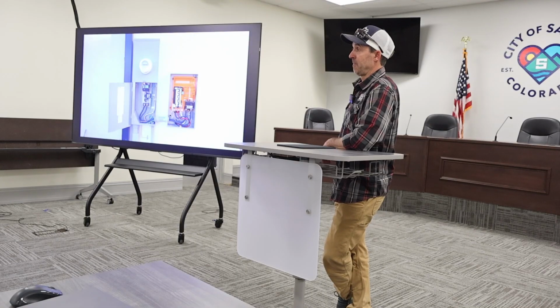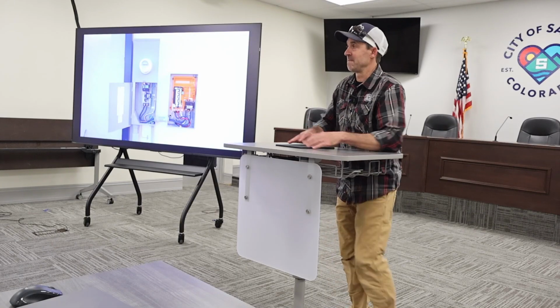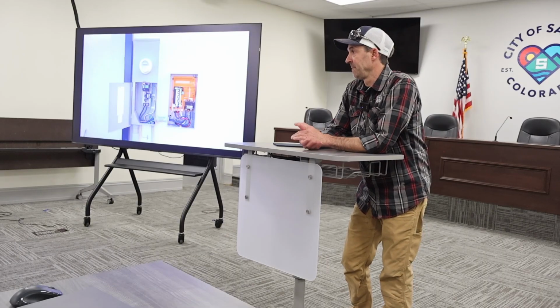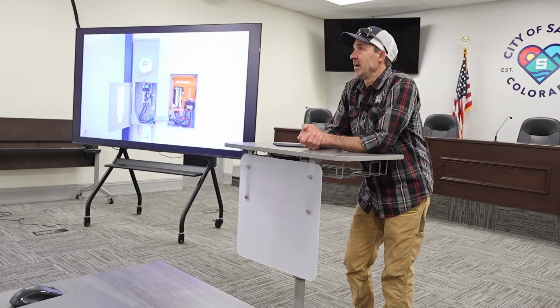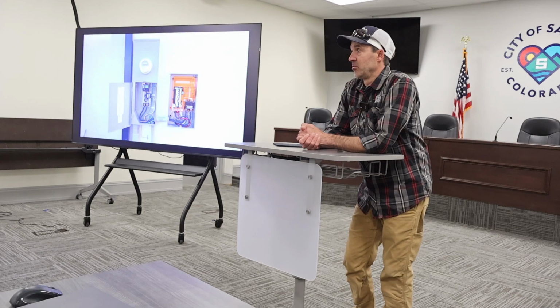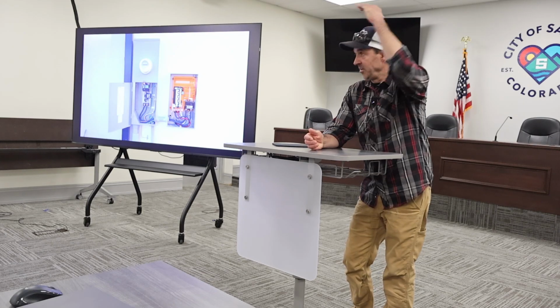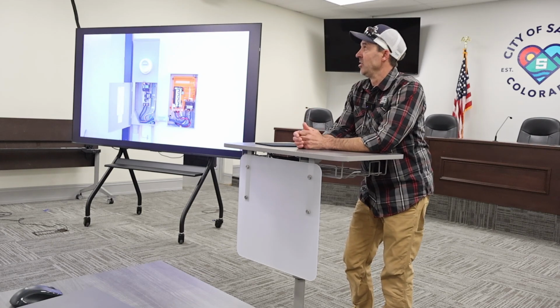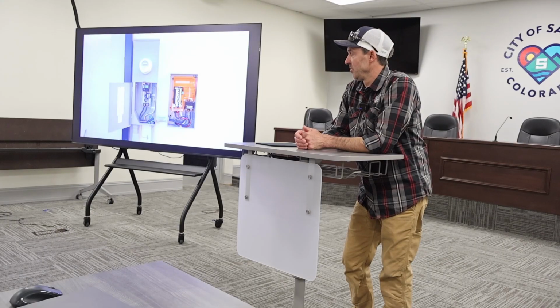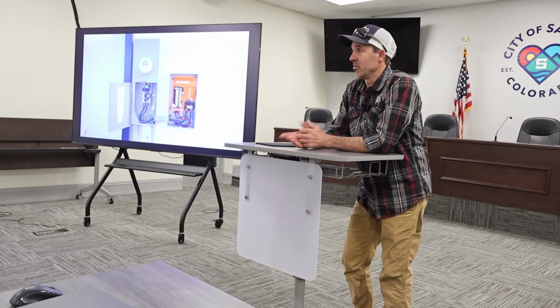You looked at a job for me when we talked about batteries. Did you tell me they couldn't go in the basement? You've got to have working clearances, typical electrical working clearance, 6.5 feet by 3 feet. And there has to be some kind of 1-hour fire rating between it and the structure.